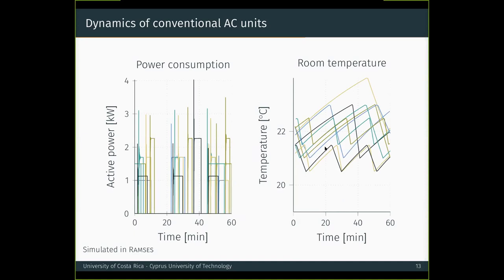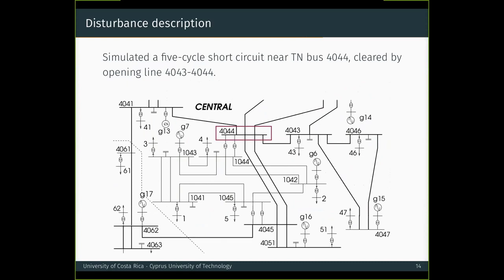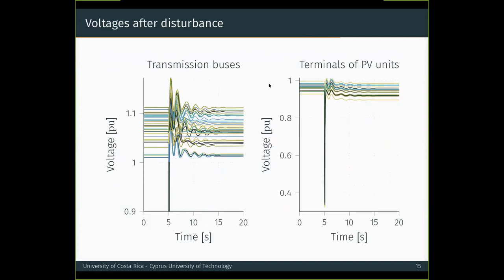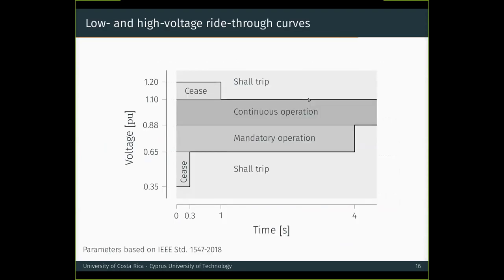Then, in order to test the response of the PV units, we simulated a five-cycle short circuit near transmission bus 4044, cleared by opening line 4043 and 4044. On the left, we show the transmission voltages and see that this was not a disturbance that led to instability. And on the right, and most importantly, we see the terminal voltages of the PV units. Since we are modeling the low voltage networks, we can capture the spreading of those terminal voltages, both before and after the disturbance. To understand the response of the PV units, we need to know the parameters of the low and high voltage ride-through curves. When the voltage exits the region of continuous operation, the units are allowed to cease to energize for 0.3 seconds and then they are required to inject power up to four seconds after the disturbance.